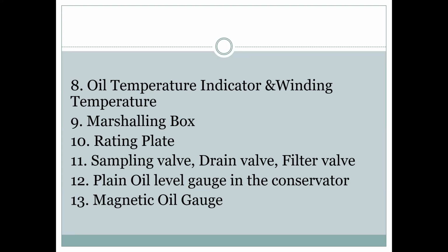For a few hours it is okay. I can rectify, I can reset the transformer and the power outage is removed. But the winding is intact. All this protection is here to protect the winding. Then the plain oil level. Oil level is the most important. The core and winding have to be dipped into the oil, and that's why the plain oil level gauge is there with the conservator.